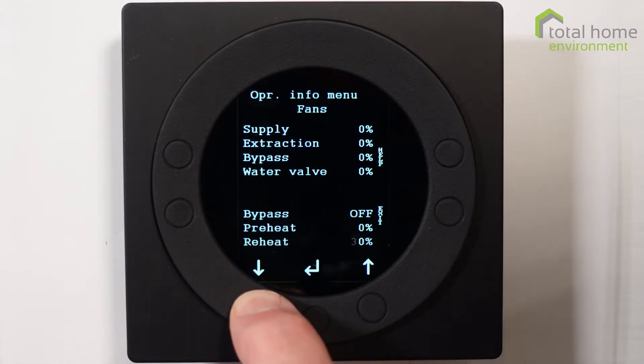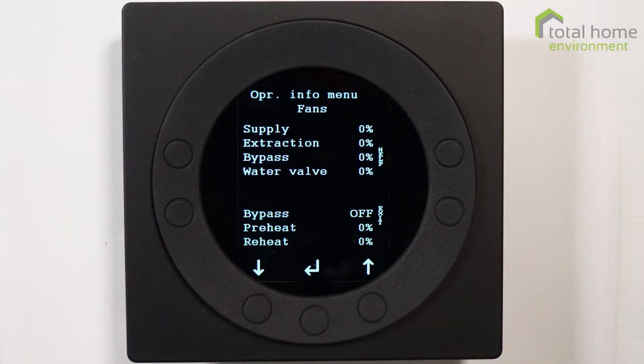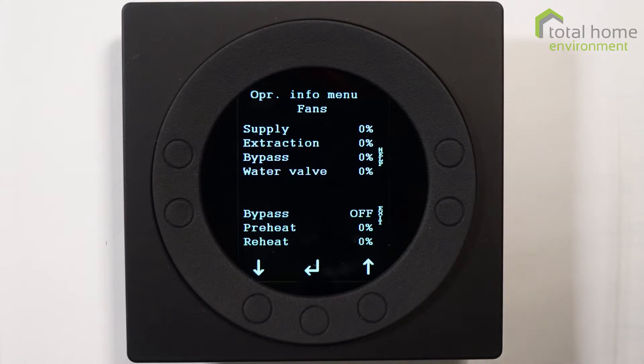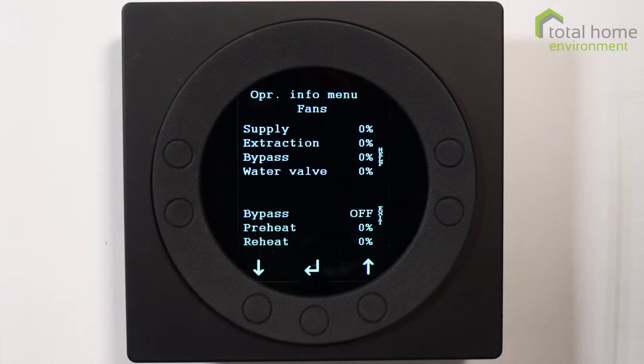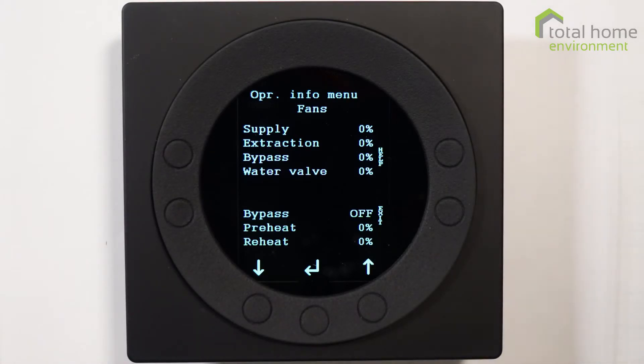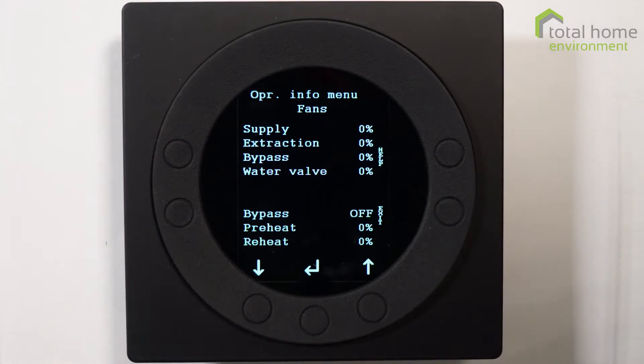If we press the down arrow it gives us another page and it tells us at what speed the fans are running. Supply is providing fresh filtered air into your property. Extract is taking the moist air out of the property, and the bypass utilizes or blocks off the heat exchanger in order to reduce the incoming air temperature. Water valve relates to systems which have water heating in addition to the system, and often that's where the T9 sensor would be used.